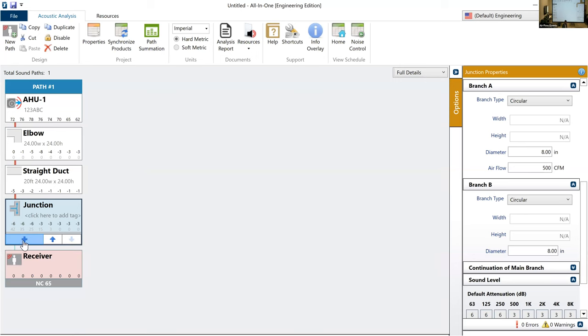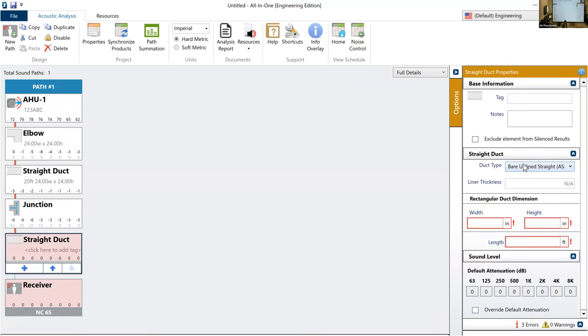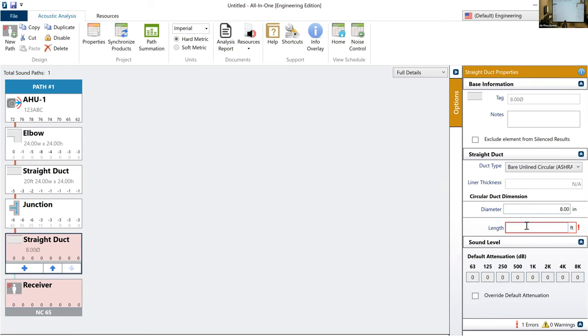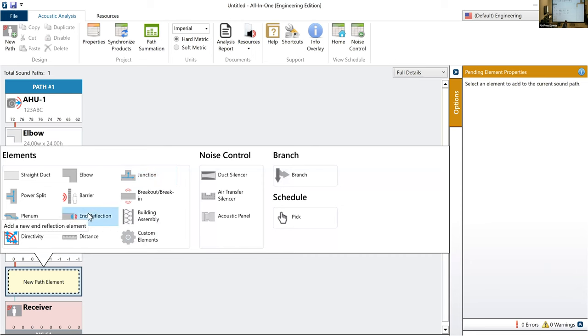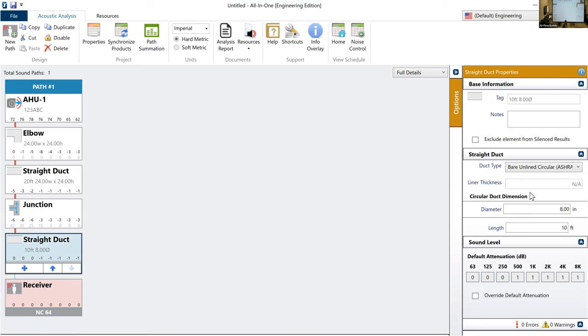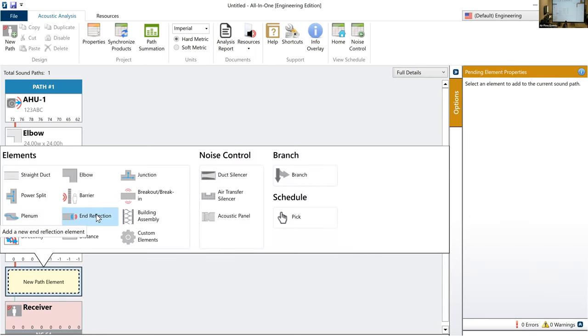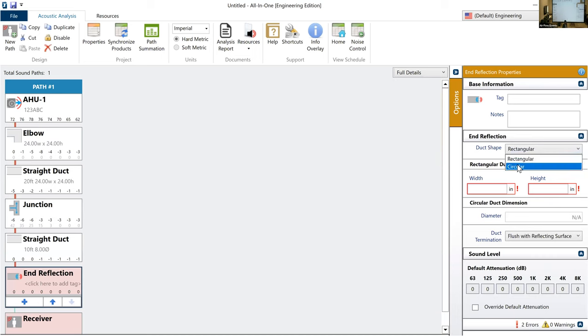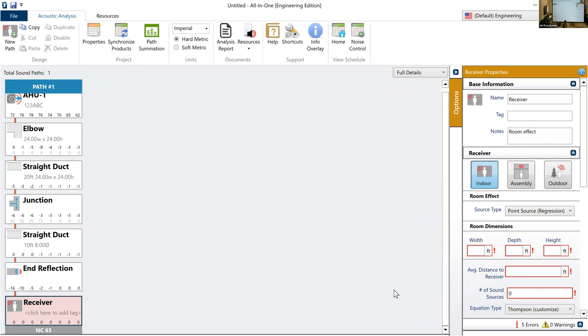And let's add another piece of ductwork. In this case, we'll say it's an unlined circular duct. I'm going through this pretty quickly, obviously, for the sake of time, but you can see building these path analyses is quite easy. You basically pick through pre-populated elements and you apply your properties as needed. At the end of our duct, we're going to have something called end reflection, which is basically that 8-inch diameter duct coming to an abrupt end, and then some of that sound energy reflecting into the space and some reflecting back into the ductwork. Finally, we're at the room itself, which is our receiver at the bottom.